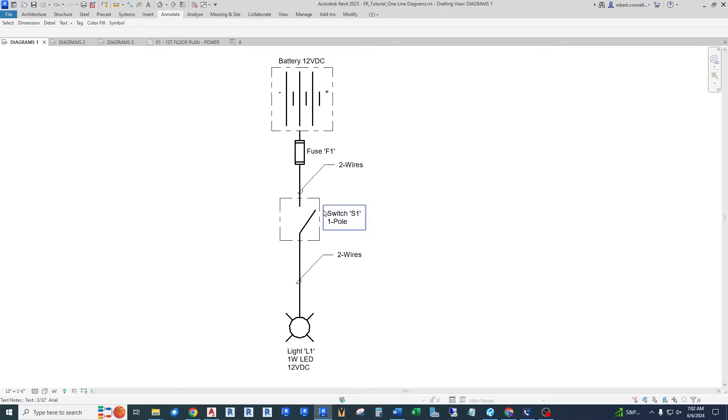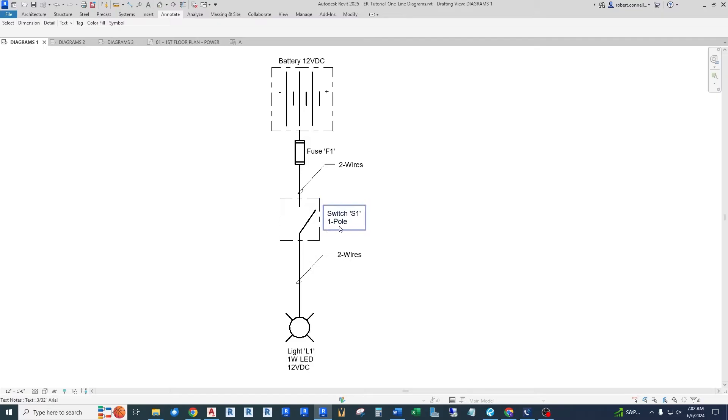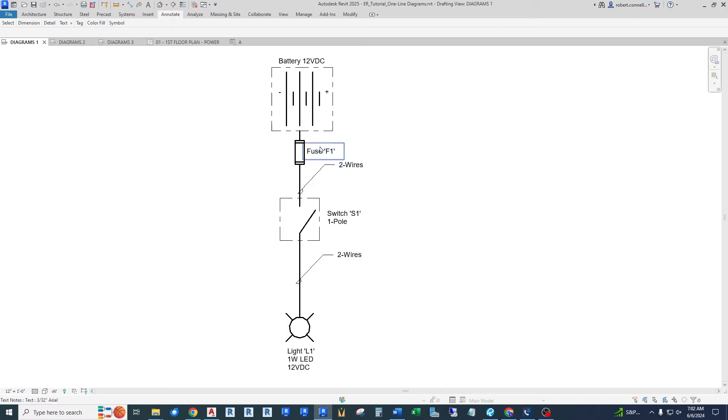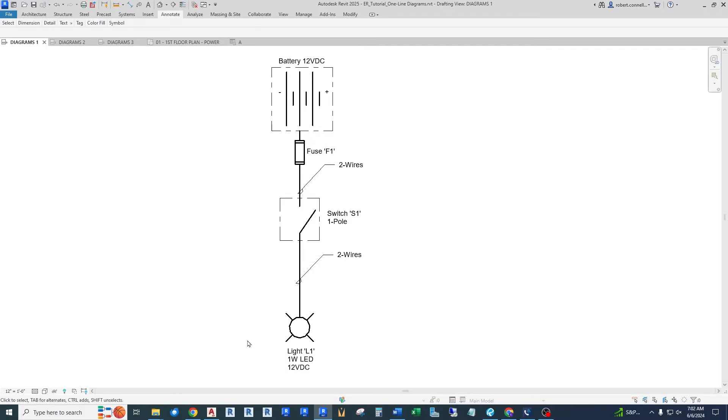To read this, you have to have the knowledge and understand that this line represents more than one wire. Maybe it's a conduit, maybe it's a cable, maybe it's a bundle, but it's representing multiple wires. And you have to know that this switch only switches the, in this case, the positive lead, not both. It's only one pole. It's only switching one wire. You know, there's two wires in here with this note. This fuse only protects the positive lead. And this, again, just understood. If these things need to be clarified, you can also have a wiring diagram for certain pieces of this, just to clarify it. But overall, this represents the source and loads and distribution in between, simply.